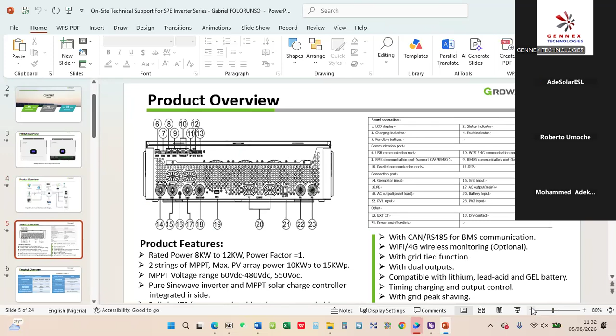The first is 8,000, the second is 12,000, and the third is also 12,000, and they have different ranges of PV capacity they can hold or sustain, we'll discuss that later. The good news is, for the very first time, like somebody asked earlier, you can go over 450, even over 500 VDC, and you are safe with the SPE. It has a tendency to handle beyond 450 volts. Meaning, if you series up your panels, it will absorb it depending on the VOC of the panel you're working with. You are sure you can go beyond 450 volts with the SPM series. The SPE can do 550 volts, so take note of that.